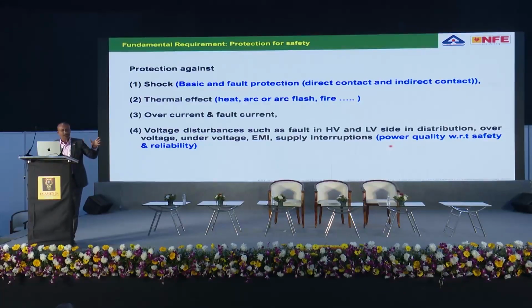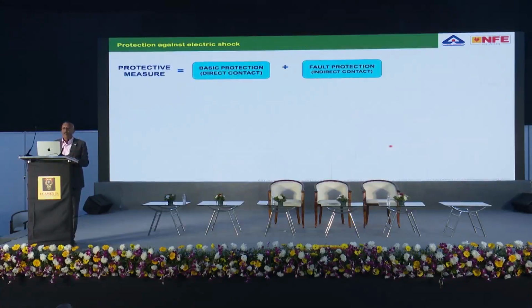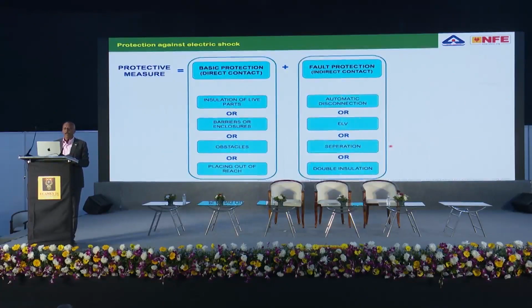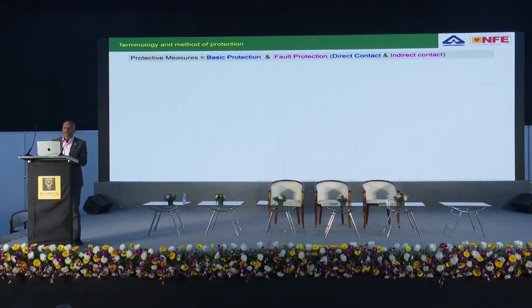This part probably looks like theory, but once we go into it, it becomes more and more complicated. For example, protective measures against shock are classified into basic protection and fault protection. For basic protection, there are different methods: insulation of live parts, enclosures, obstacles, placing out of reach. Fault protection means there is a good electrical installation, but there is a fault. During a fault, what you should do, I explain with a picture here.